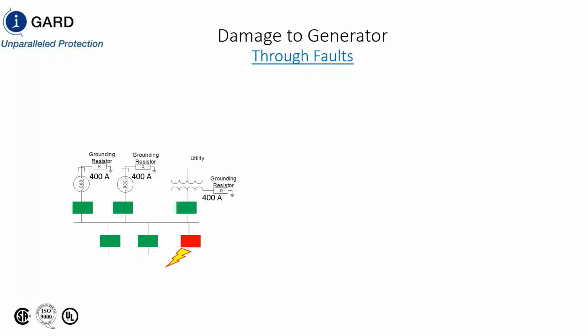Both the Canadian Electrical Code and the National Electrical Code state that if you have a ground fault on a source which is greater than 150 volts to ground and greater than 1,000 amps, you must have ground fault protection. So you have to trip right away.